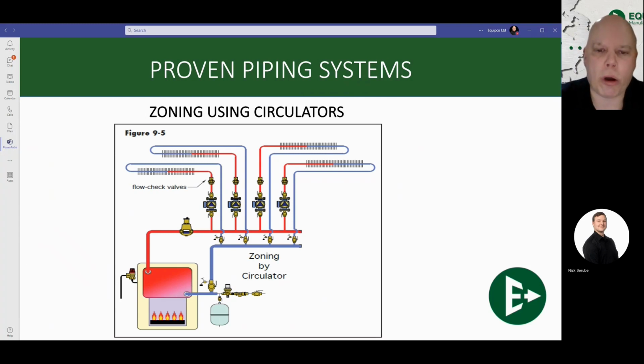This one here is a much more common type of application. This is referred to as just a standard zone system, or what's called moose antlers, where you have one antler being your supply branch, and then you have the other antler being your return branch. That blue is your return, the red is your supply. And off each of those supplies, you've got a big pump sending it out into radiant zones or air handlers or radiators, whatever it is, where each of them sees the same temperature, and then each one comes back onto the return. Extremely popular style. Even nowadays, we see this all day, every day.